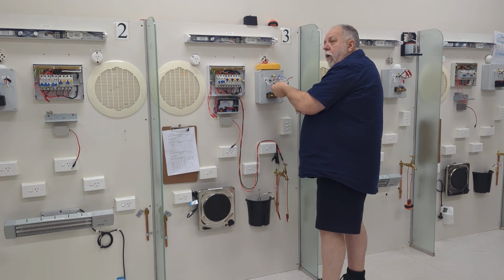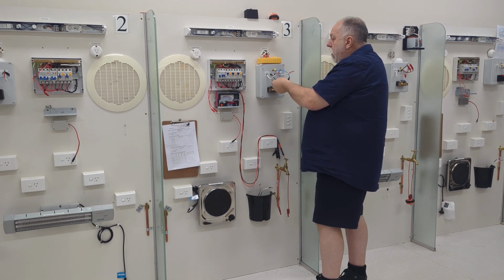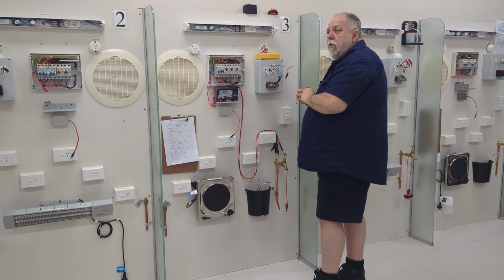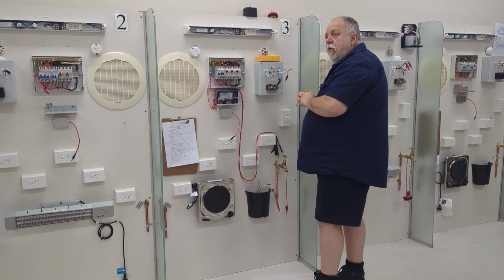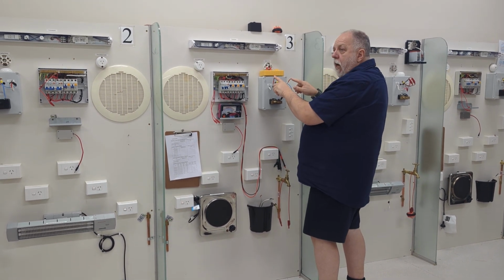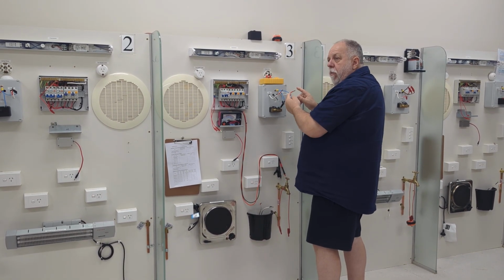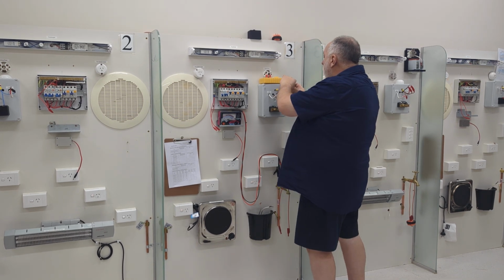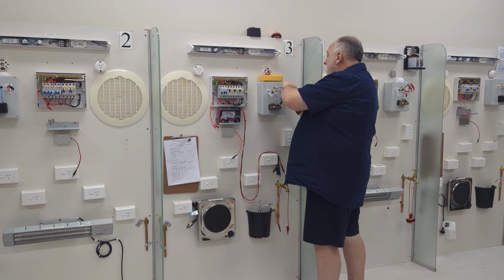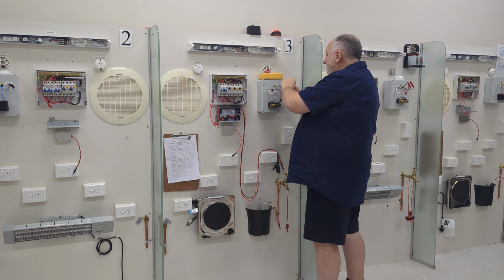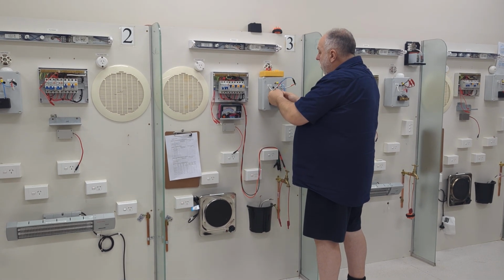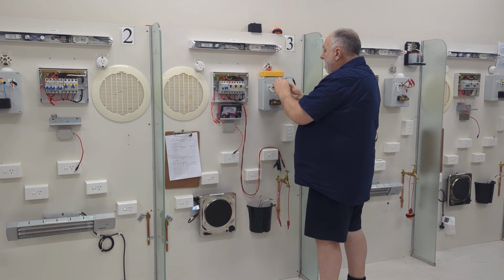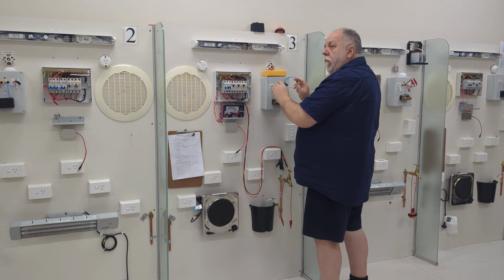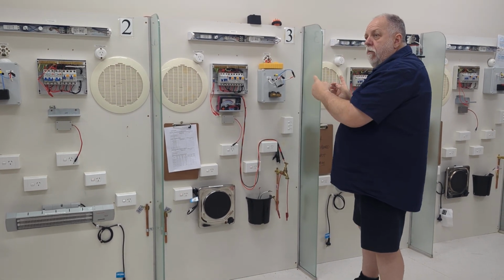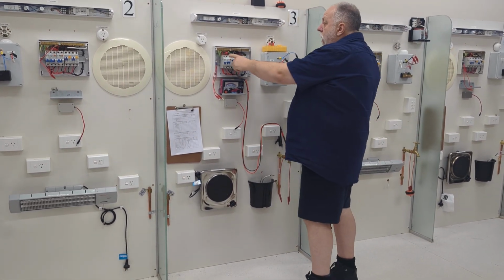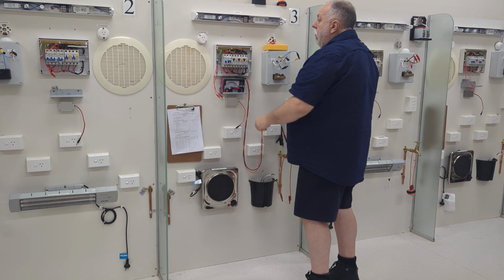The little neutral we got here, which is usually a smaller size, 4 or 6 mil, that's what supplies the voltage difference. Do you understand what I'm getting at? That's my current running through here. I now need to provide a power. So what I'm going to do is bridge all those 3 out, which is an easier place to do. That means I've bridged my active and neutral out. I now have it from the pit. Both cables at the pit are now joined together. I have it all the way back to the switchboard and I have active and neutral.